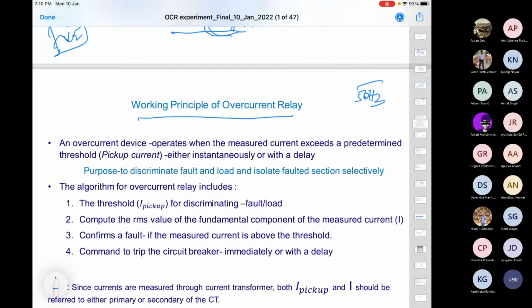No, a very good question. Consider that the fault progresses, and the relay has to make a decision. If the relay has not decided till now, then the relay goes on acquiring data till the decision is taken. So it is not one window or two windows. It is a continuous window, you can say a moving window, till the relay takes a decision. Furthermore, even after the relay takes a decision and commands the circuit breaker to open, the window still goes on till the current becomes zero.